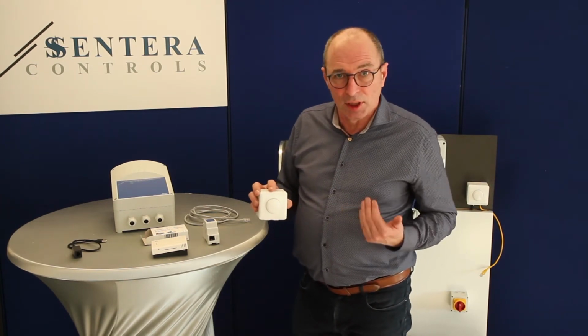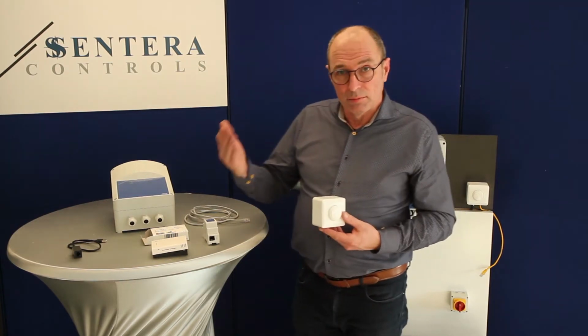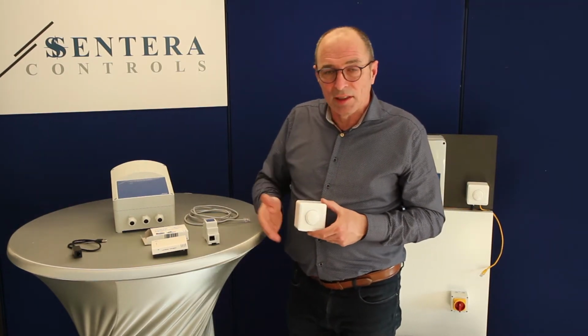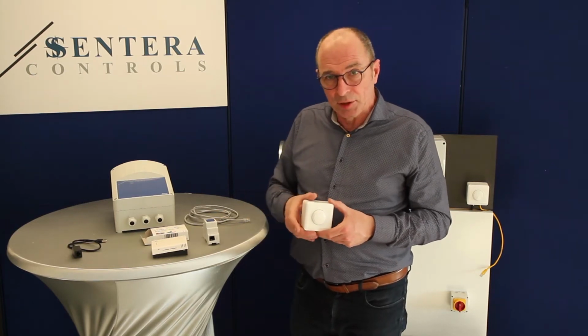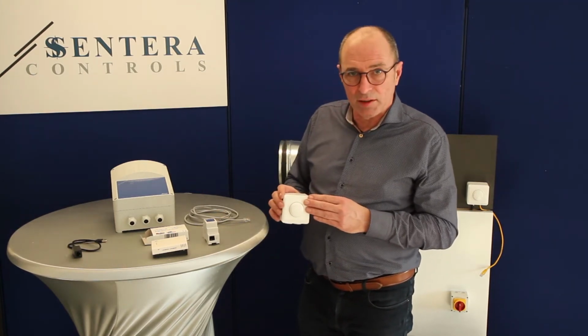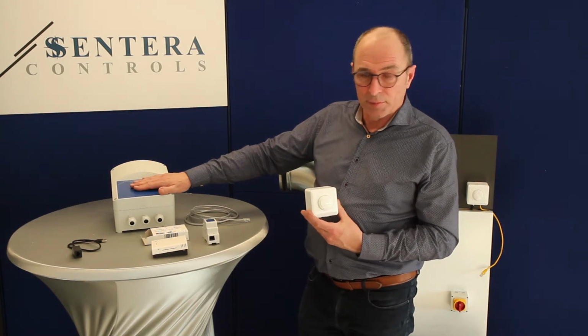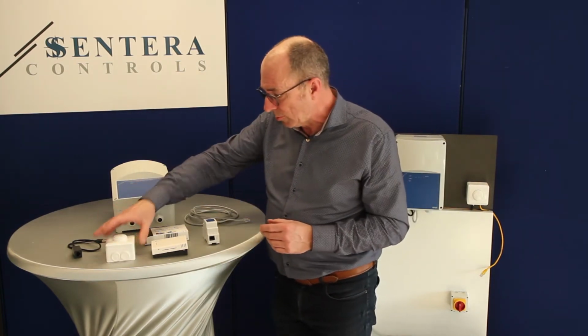The Modbus signal can be sent over a distance of 1000 meters. And in case the Modbus signal's amplitude weakens too much anyway, it can easily be boosted up with a repeater. So you can put this controller very far away from the fan speed controller itself.